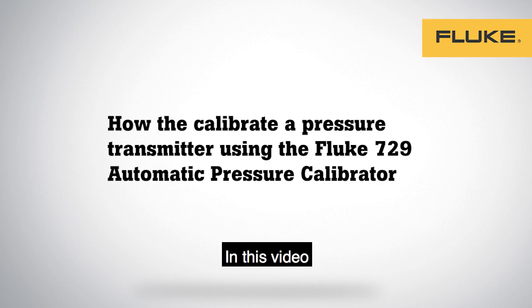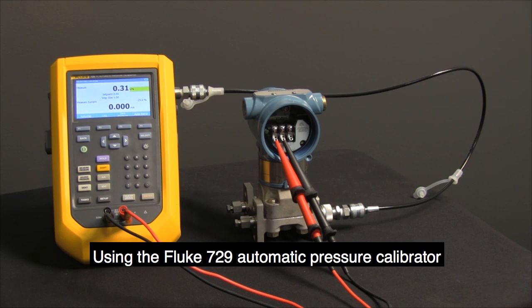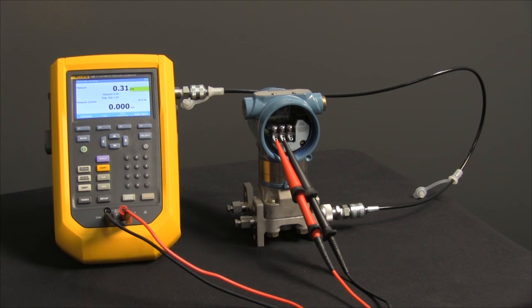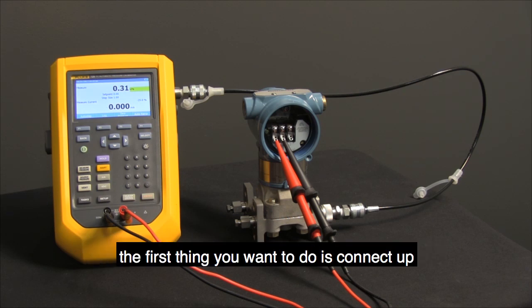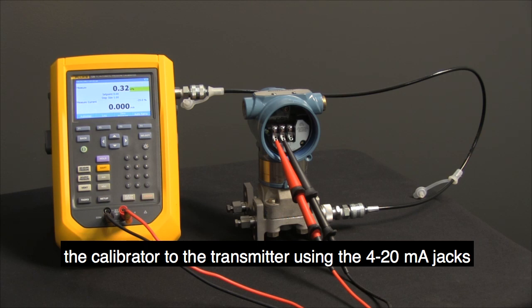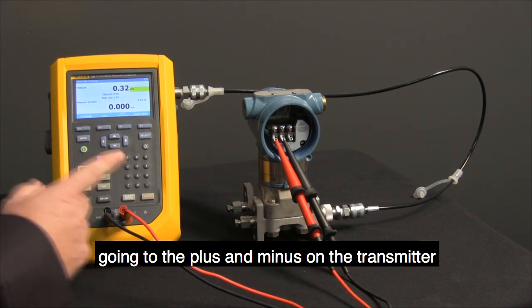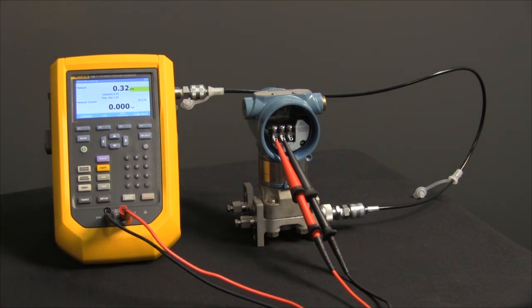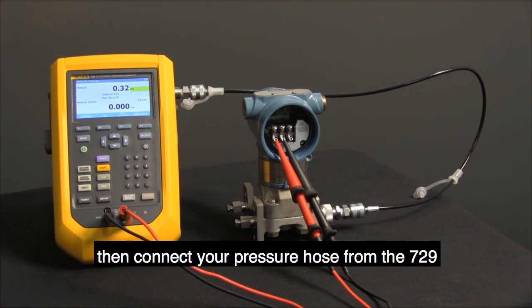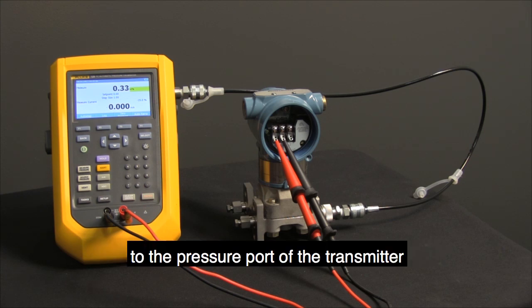In this video, we're going to calibrate a pressure transmitter using the Fluke 729 Automatic Pressure Calibrator. The first thing you want to do is connect up the calibrator to the transmitter using the 4-20 milliamp jacks, going to the plus and minus on the transmitter. Then connect your pressure hose from the 729 to the pressure port of the transmitter.